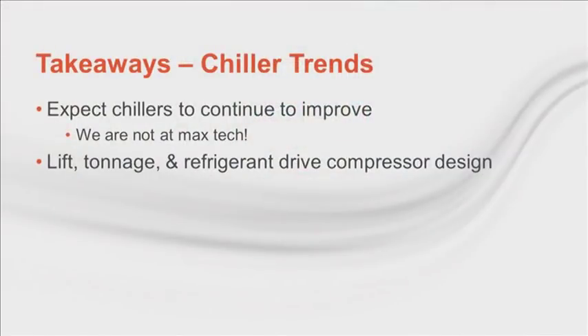exceed stated minimum efficiencies. Now, one of the challenges manufacturers face as they drive towards max tech is compressor design. We learned impeller design and therefore compressor design is driven by an application's conditions as defined by lift and desired tonnage. Something many may have not known was that refrigerant choice is another significant input to compressor design, driving choices downstream. The result?